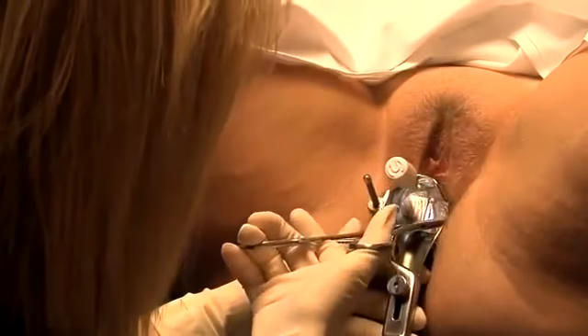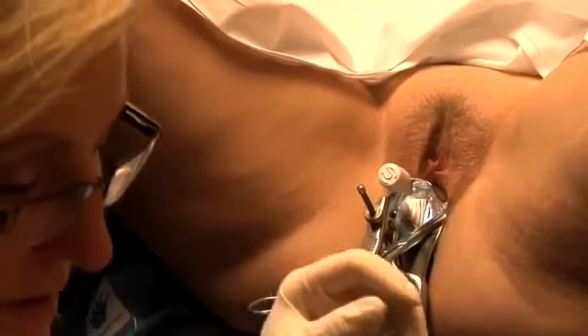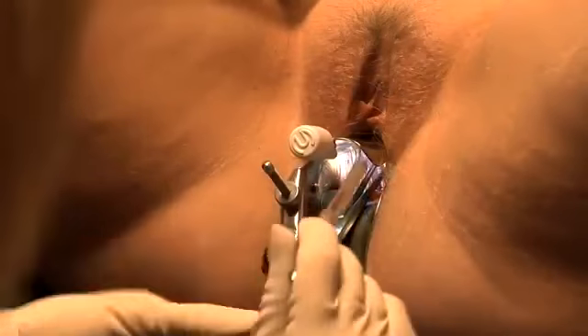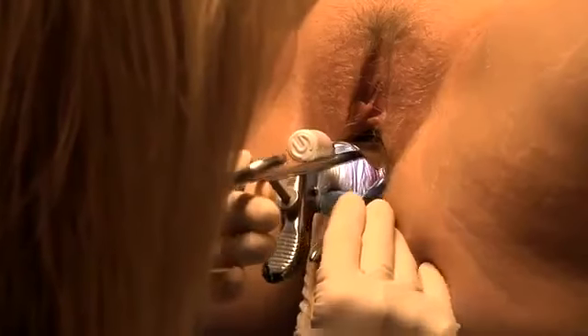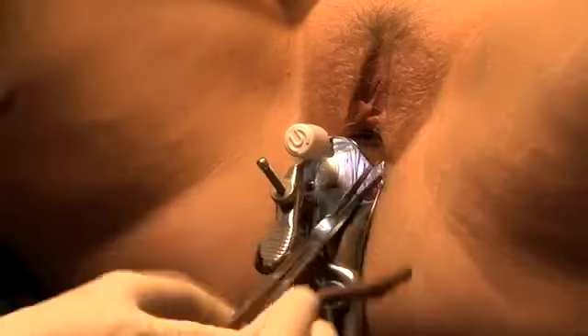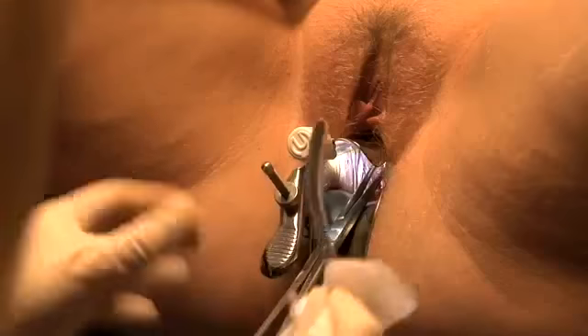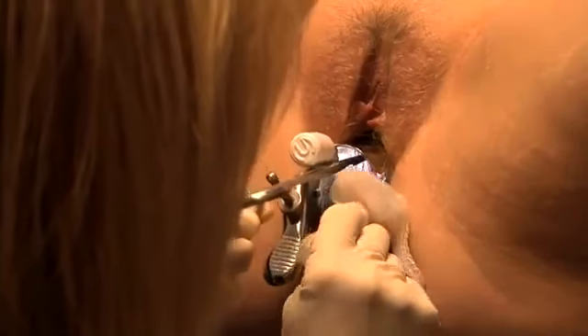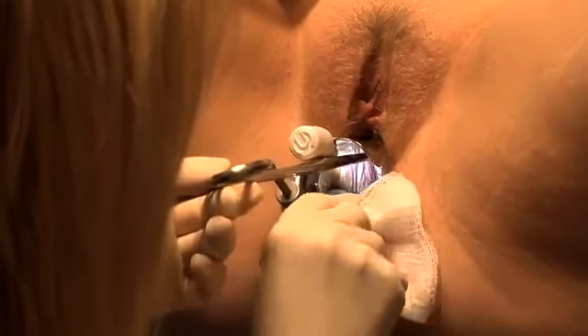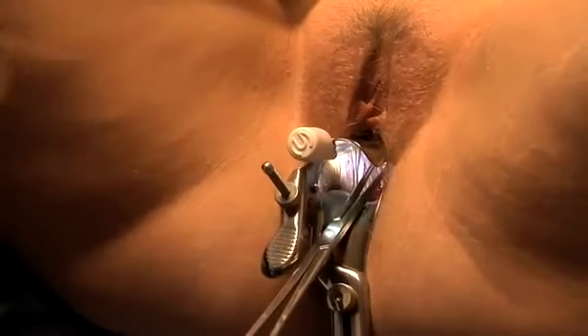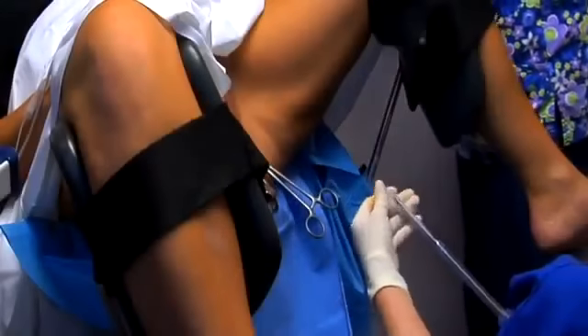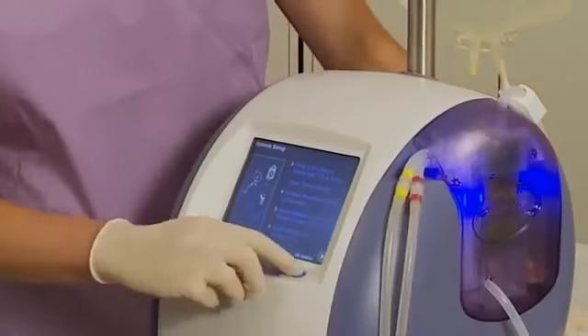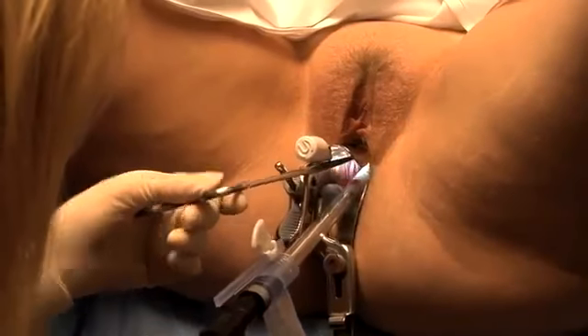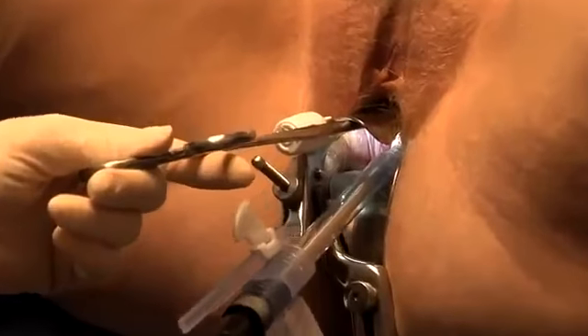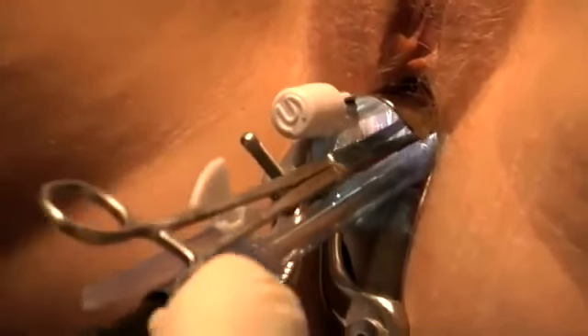Attach the tenaculum to the cervix. Dilate the cervix to approximately 8 millimeters, or 24 French, being careful not to over-dilate. It is recommended to use Hegar dilators. Please be mindful when advancing the dilators to avoid uterine perforation. Next, remove the sheath cap and press the right console button to initiate diagnostic hysteroscopy, and carefully insert the sheath into the cervix. The sheath should always be advanced under direct visualization.